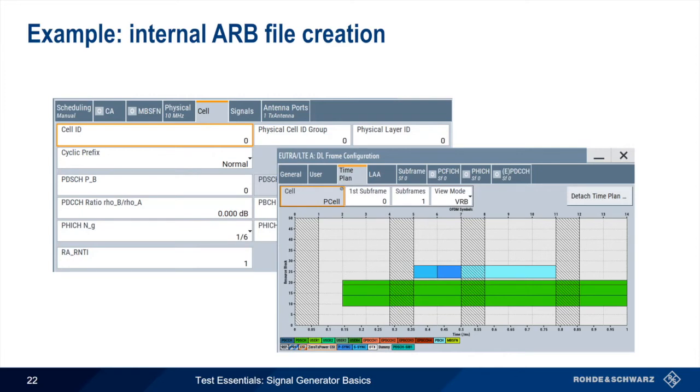Being able to perform this kind of signal configuration directly on the generator, as opposed to using external tools, greatly increases the ease and efficiency of defining vector modulated signals. The end result of this process is an arbitrary waveform that can be immediately generated by our instrument and/or saved for future use.